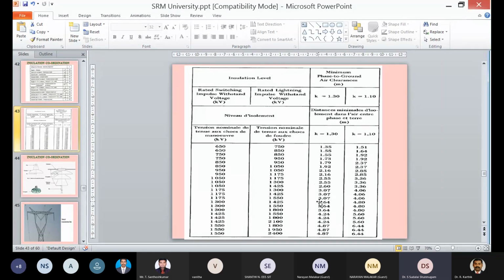And for a 400 kV system, they define the phase to ground clearance as 3.07 meter. I repeat, for a 400 kV system, phase to earth distance should be 3.07 meter. It means that for a 400 kV system, the distance between the tower cross arm and the conductor should be only 3.07 meter; it should not be more than that. If we consider a safety factor of 1.30, then the tower to line distance is 3.07 meter. So within this 3.07 meter, we have to keep the insulation.